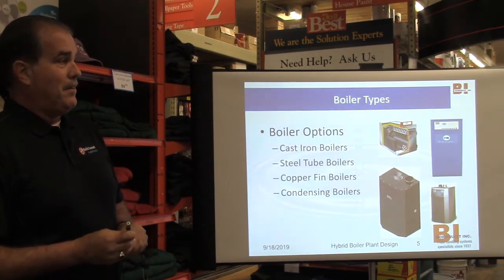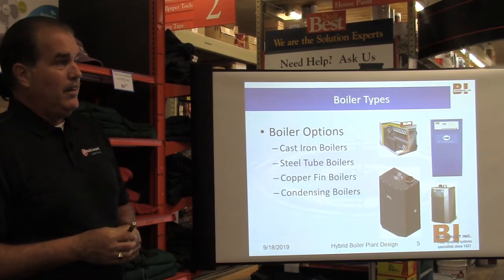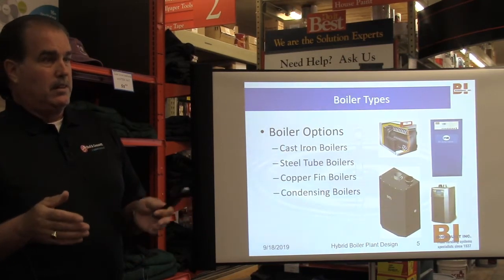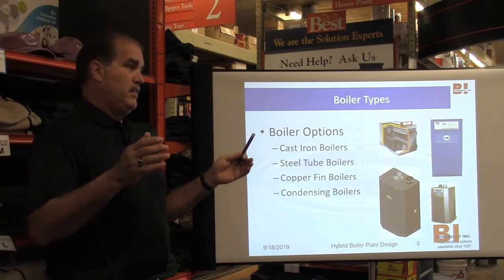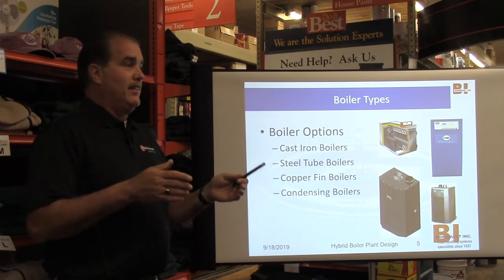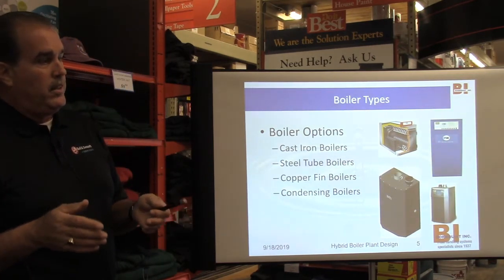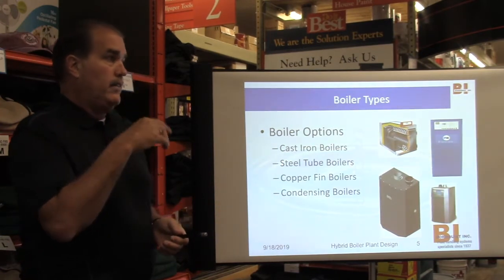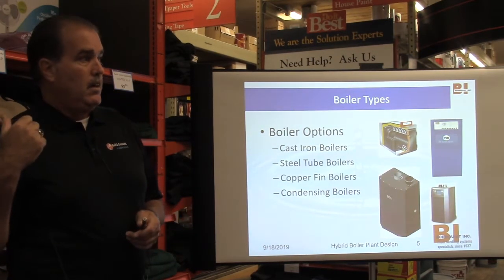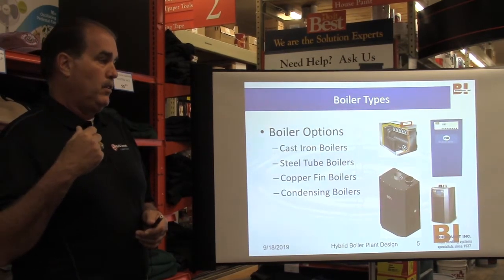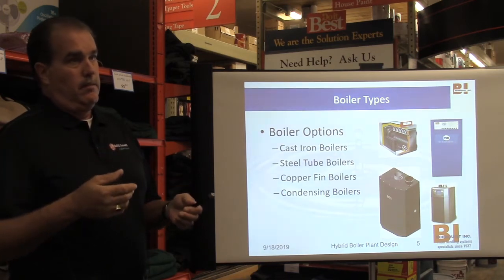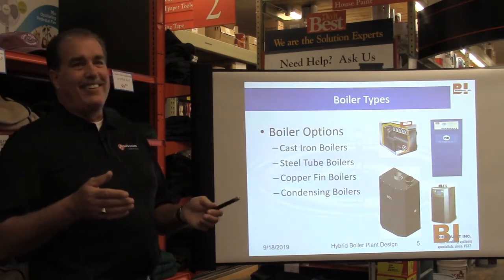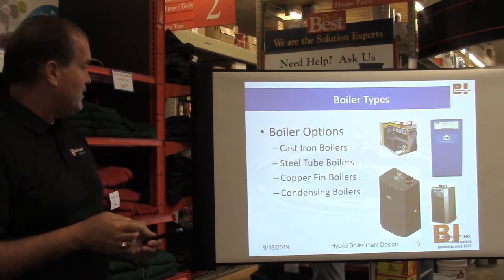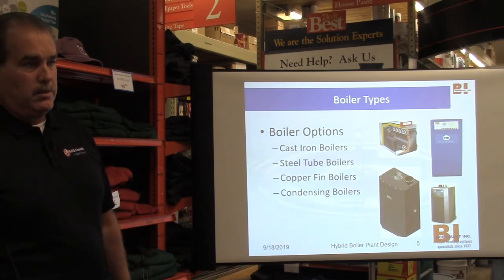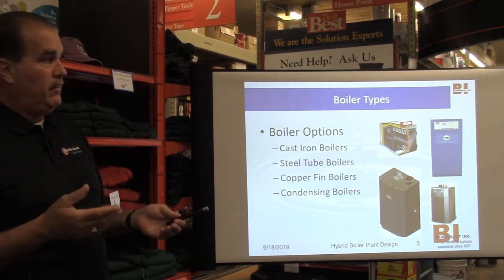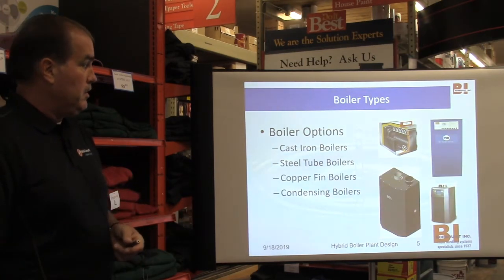And then I did already touch on condensing boilers, which are the latest craze in the industry. I remember when I used to teach many, many years ago, I always said the boiler industry moves at a glacial pace. It hasn't changed much in the last 50 years. Well, I'm happy to say that in the last 15 years, it has probably changed more than it did in the prior 50. A lot of that is technology coming over from Europe, because their cost of fuel is a lot more expensive. Here, natural gas used to be expensive, and nowadays it isn't that expensive, but it's still an expense. If you're heating a building, particularly if you're a building owner, depending on how you have your contract set up, you want your building to be as efficient as possible.